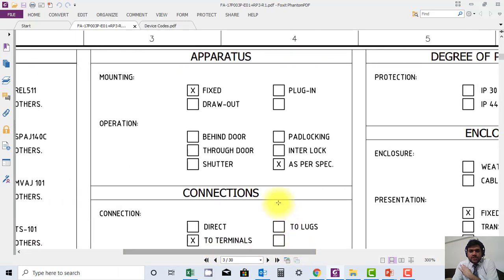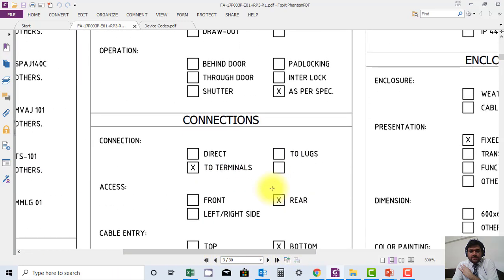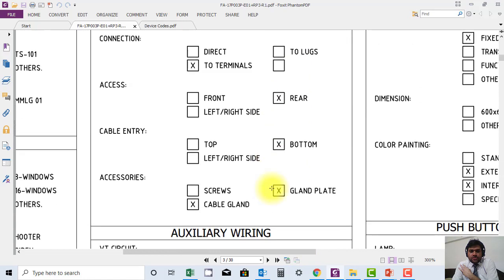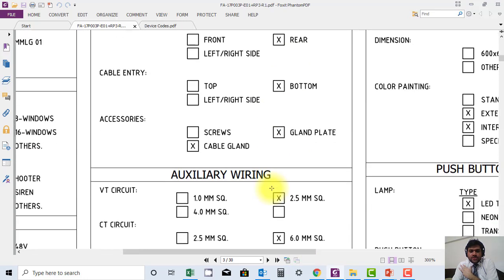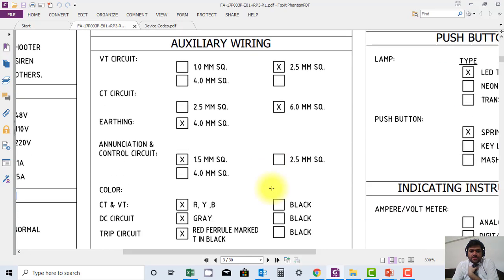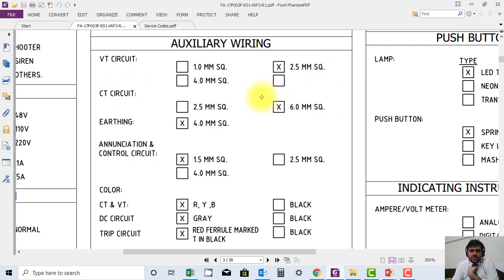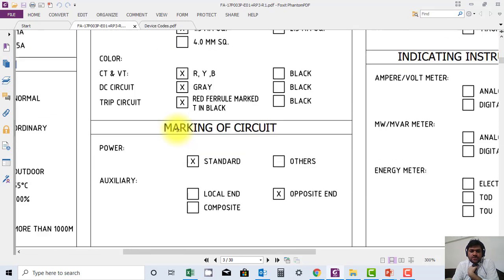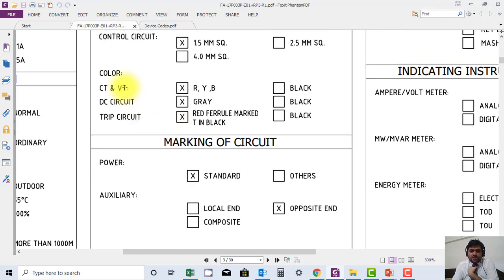You can find it here. This document is available, so you can further check it and discover more. Another thing: for example, they are saying that VT wires are of 2.5 square mm and CT is of 6 square mm. You can see wiring is done through 4 square mm. This information and color coding is also mentioned.